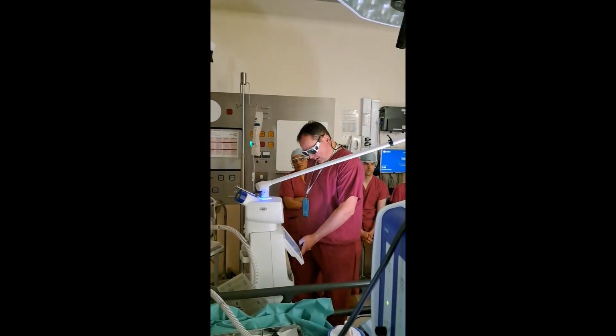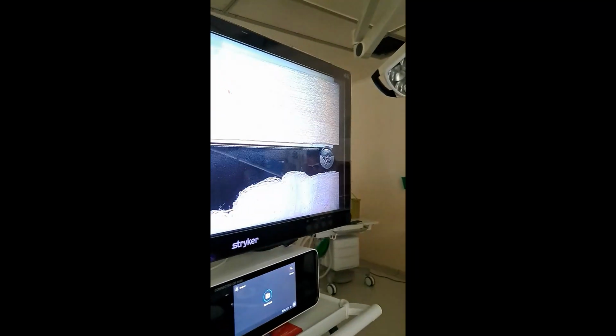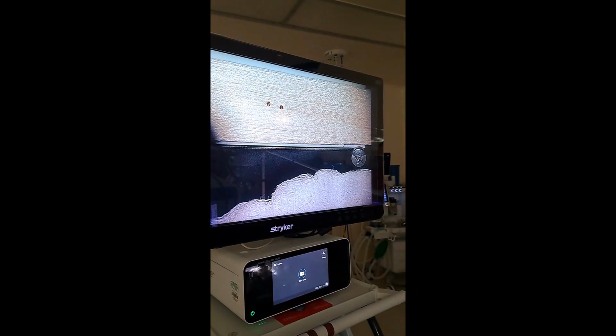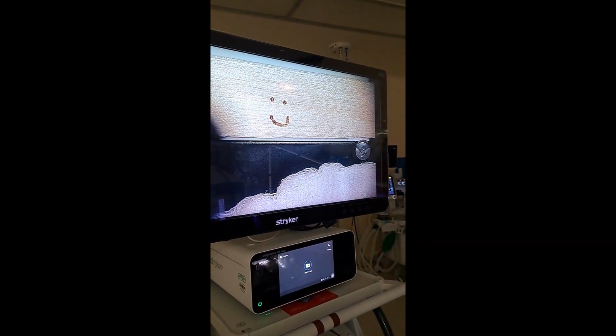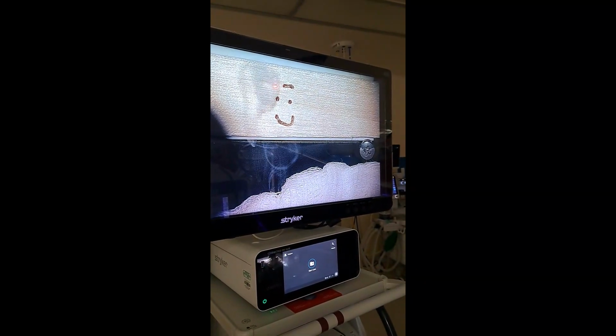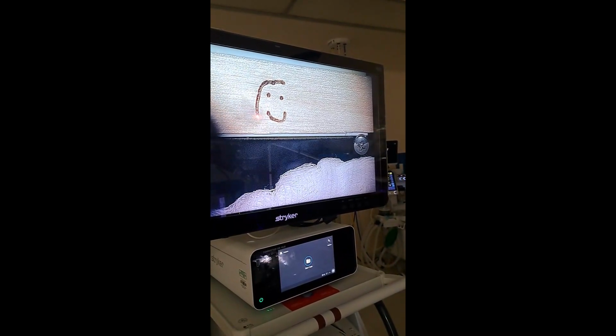So everybody's got their glasses on. We've got our laser check, got our wet patches around. Do your check. Ready when you are, Steve. Okay, super pulse continuous, 2 watts. Laser's ready. Lovely. I normally just do a smiley face because I don't get out much. So you want a pinpoint. Your laser test.